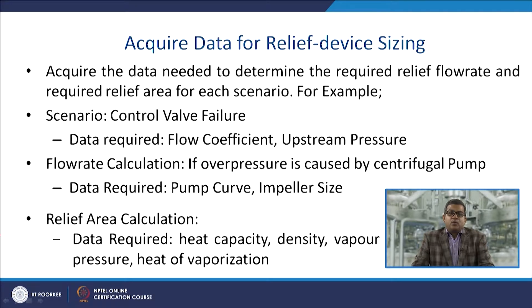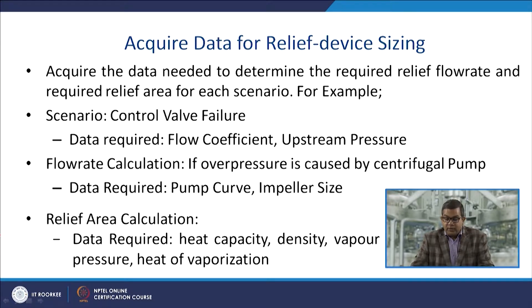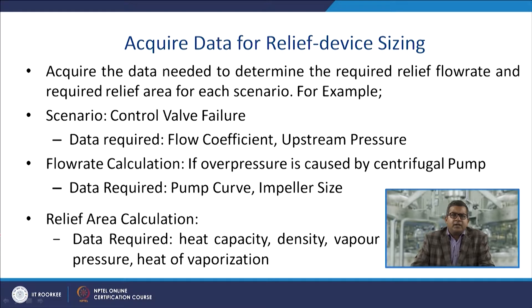The next aspect is acquiring data needed to determine the required relief flow rate and relief area for each scenario. For example, if the scenario is a control valve failure, the data required includes the flow coefficient and upstream pressure for flow rate calculations. If overpressure is caused by a centrifugal pump, the data required includes the pump curve and impeller size.